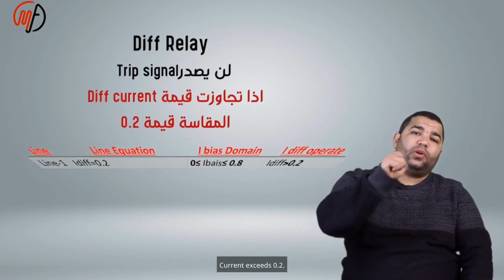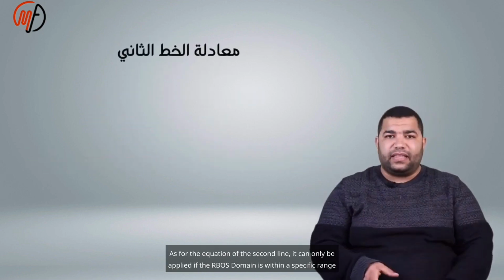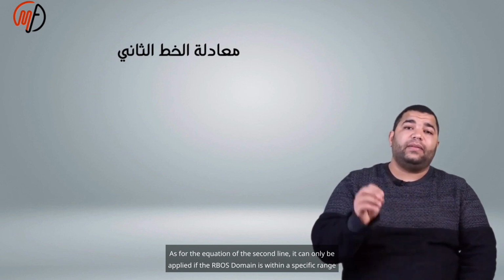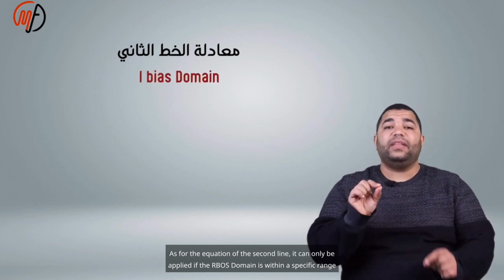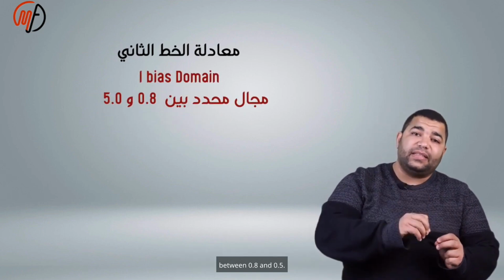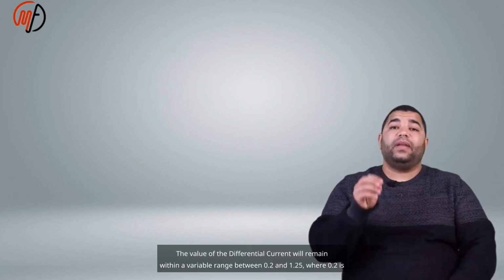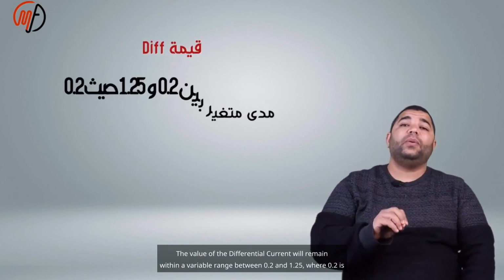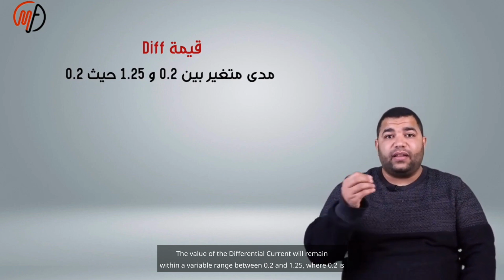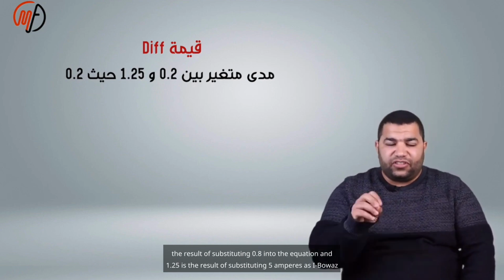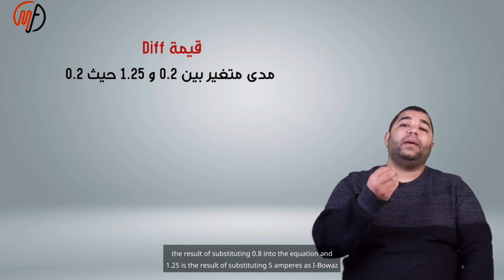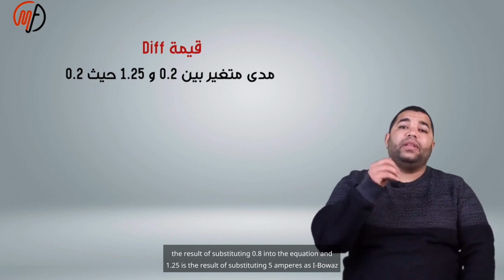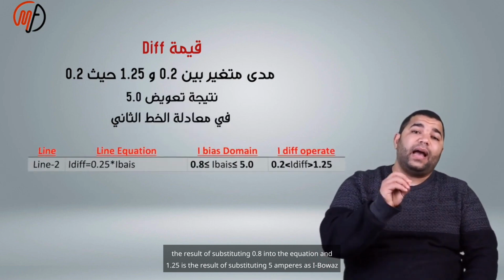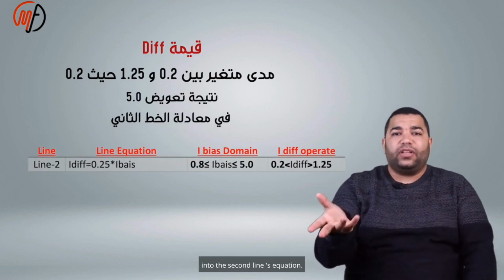exceeds 0.2. As for the equation of the second line, it can only be applied if the I bias domain is within a specific range between 0.8 and 5. The value of the differential current will remain within a variable range between 0.2 and 1.25, where 0.2 is the result of substituting 0.8 into the equation, and 1.25 is the result of substituting 5 amperes as I bias into the second line's equation.